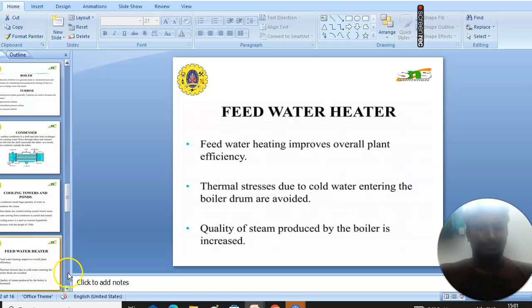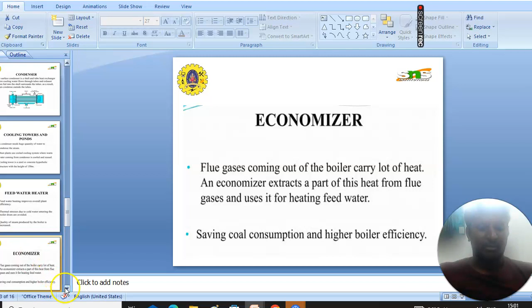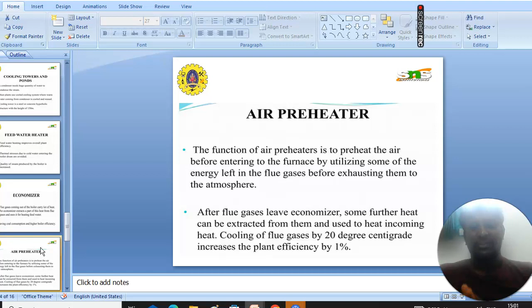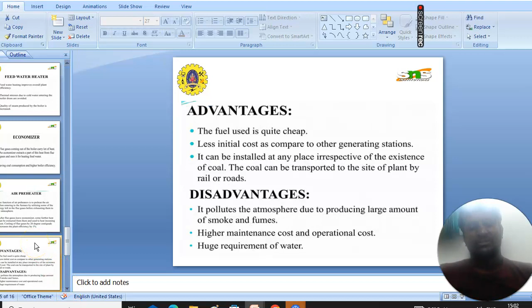The economizer is also used in the power plant. Why it is used: flue gas coming out of the boiler carries a lot of heat. An economizer extracts a part of this heat from the flue gases and uses it for heating the feed water. It is mainly used to save coal consumption and give higher boiler efficiency. The function of the air preheater is to preheat the air before entering the furnace by utilizing some of the energy left in the flue gases before exhausting them to the atmosphere. Cooling of flue gas by 20 degrees centigrade increases the power plant efficiency by 1%.